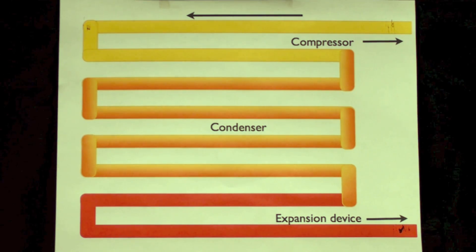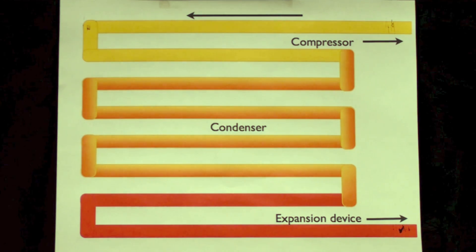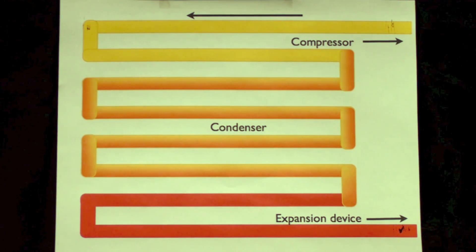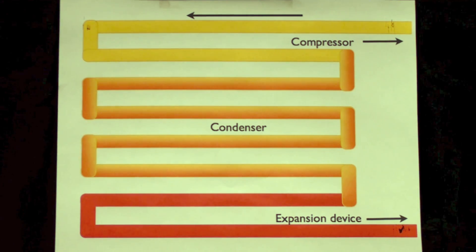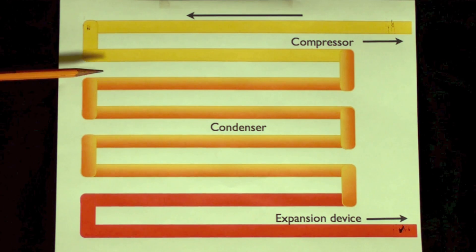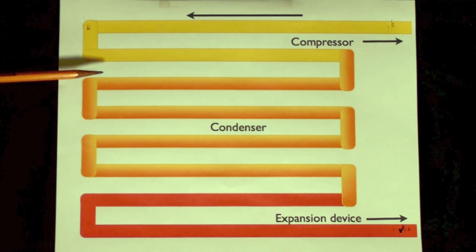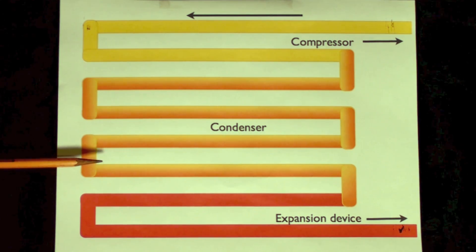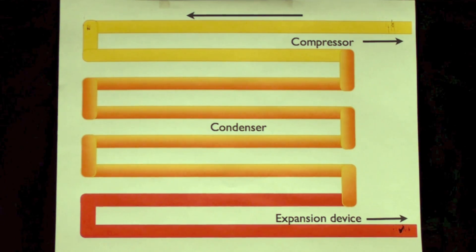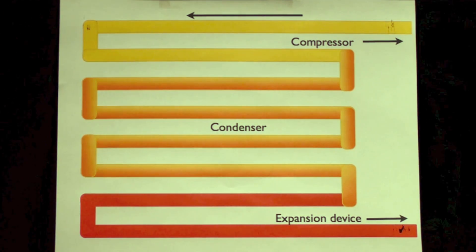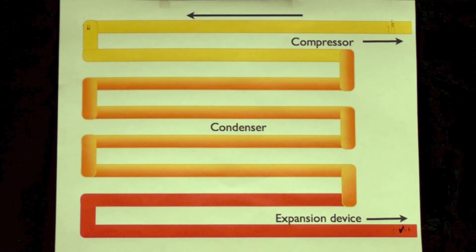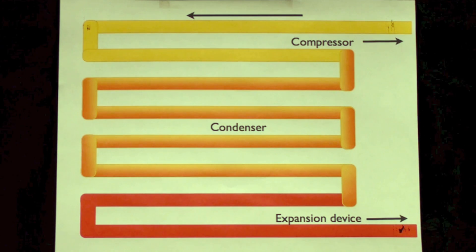That's the heat of compression. That's the heat energy that the refrigeration compressor used to compress the gas. So it has to get rid of that first, then it gets rid of all the heat that it absorbed in the evaporator, and then it subcools. So that's the condenser. Probably the next one we'll talk about will be the evaporator.